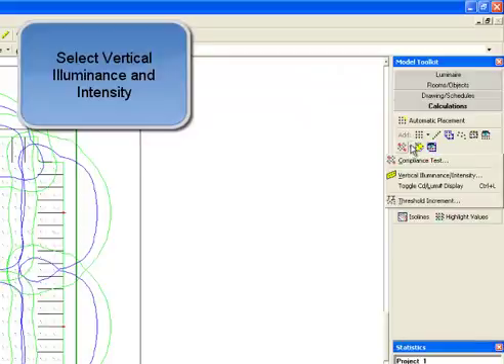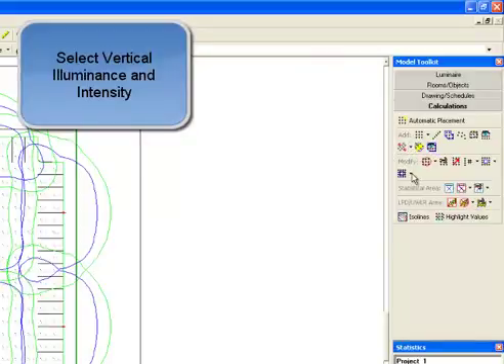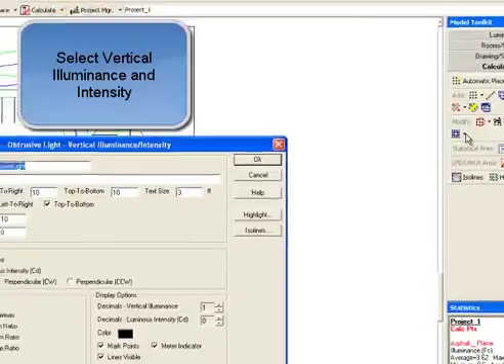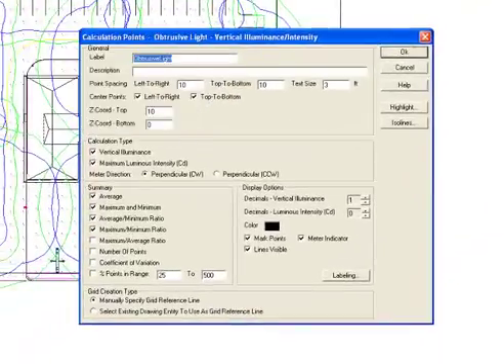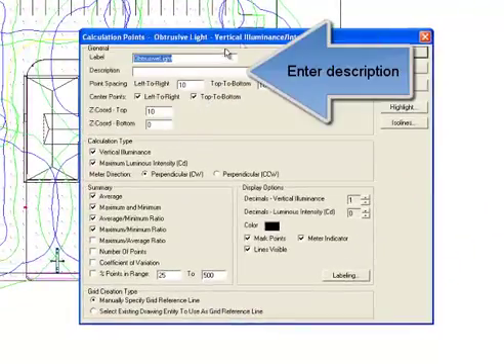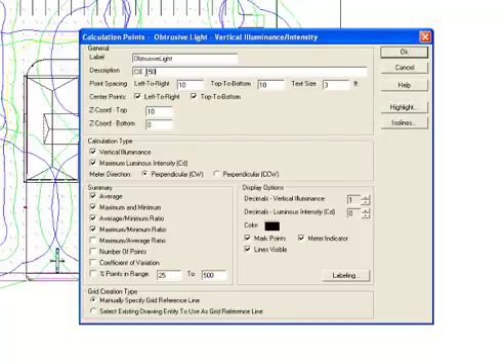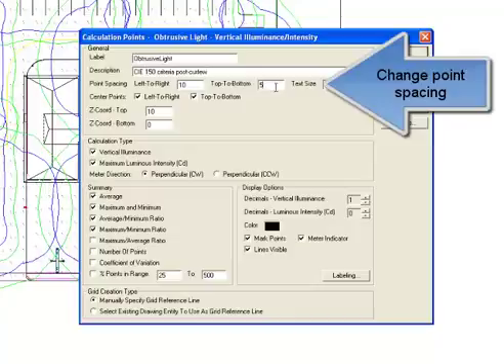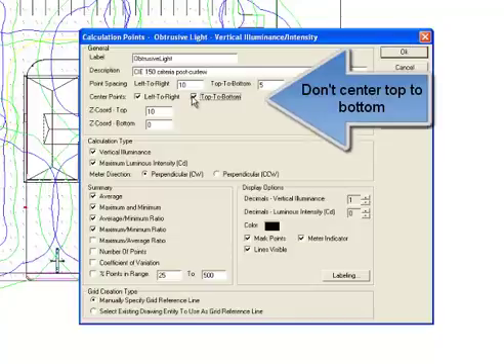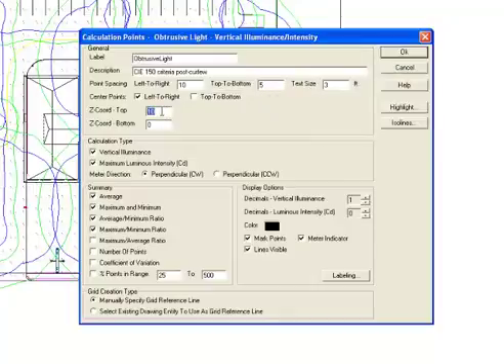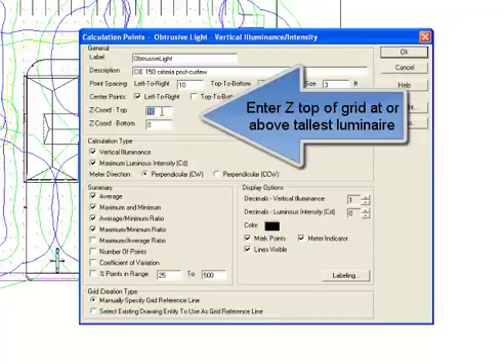Select vertical illuminance and intensity and enter a description. Change the point spacing to 5 feet vertically. Don't center the points top to bottom. The grid will go from Z equals 0 to above the tallest luminaire at Z equals 30.